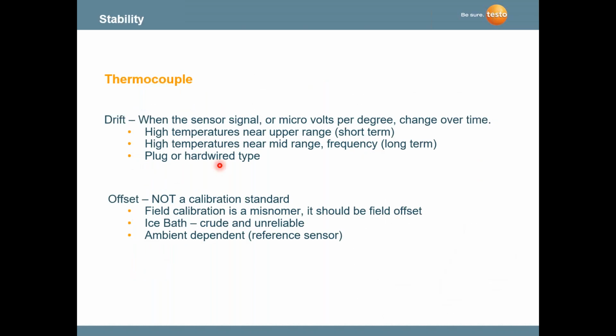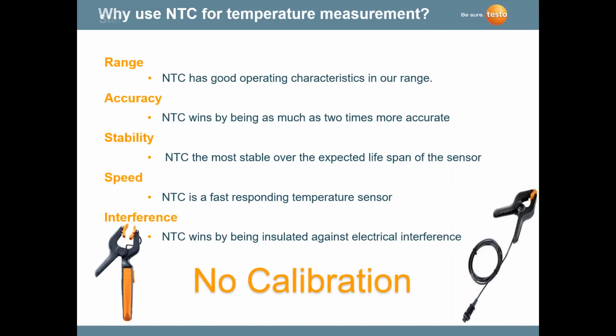Just a graph showing that a thermocouple can drift over time because of the two dissimilar metals. There is some offset, and when there's any type of offset, we've got to calibrate. We've got to calibrate a thermocouple periodically, once a year if preferable. It's tough to calibrate a thermocouple. There's no real calibration method other than ice bath, which is kind of unreliable, or maybe boiling water, depending on what elevation you're at. But you do have to calibrate thermocouples.